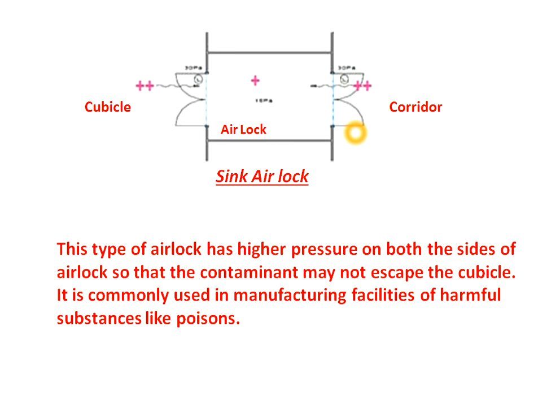The third type is sink airlock. In a sink airlock, the airlock has minimum pressure compared to its surrounding areas — the corridor and cubicle. The cubicle is indicated by two-plus and the airlock by one-plus. For example, if the airlock has 15 pascal pressure, the cubicle will have 30 pascal and the corridor will also have 30 pascal. This type is mostly used in areas where harmful substances are manufactured, such as poisons and other harmful medicinal products. This is all about today's topic — the concept of airlock and its function.